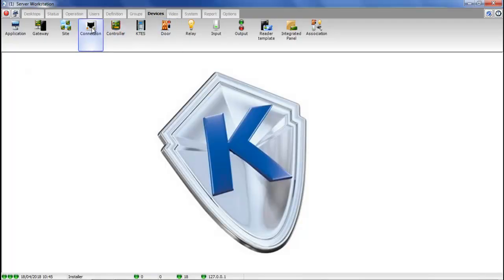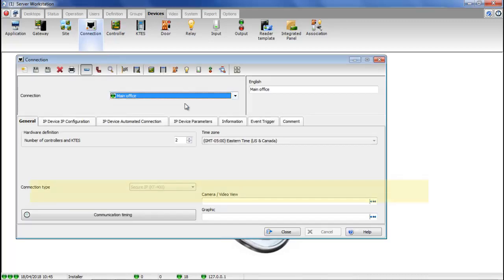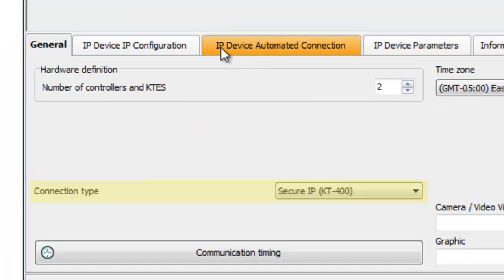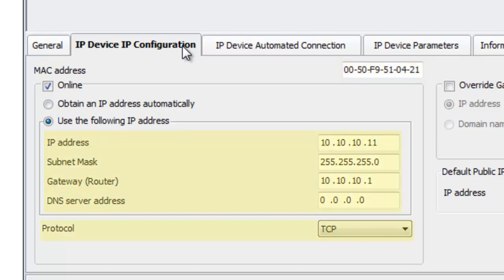Now go to devices, connection, and select your connection. Verify the connection type to make sure it's the appropriate one. Go to IP device, IP configuration. Validate the MAC. It does not auto-populate. You have to enter it yourself. Make sure the online box is checked, and verify the IP address that's selected there, with the subnet, and gateway, and protocol.